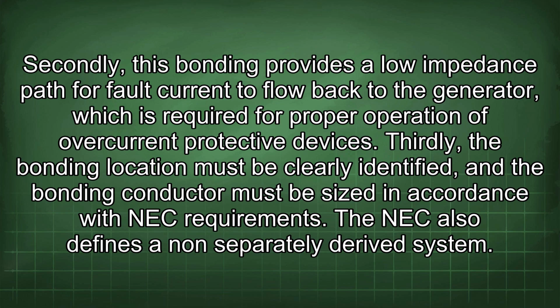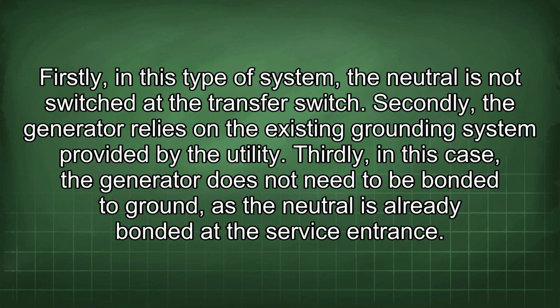The NEC also defines a non-separately derived system. Firstly, in this type of system, the neutral is not switched at the transfer switch. Secondly, the generator relies on the existing grounding system provided by the utility. Thirdly, in this case, the generator does not need to be bonded to ground, as the neutral is already bonded at the service entrance.